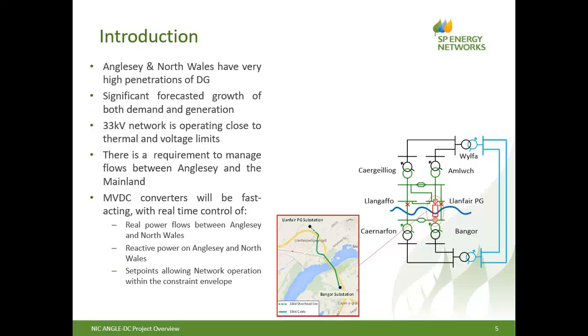We've got the added complication that when Wylfa, the new Horizon nuclear station, comes on stream, the output of that being about 2.8 gigawatts will actually cause about 50% of the circuit capacity on the 33 kV to be used up just on the kind of leakage parallel path of the power transmission from Wylfa across into mainland Wales and England. So one of our solutions to deal with this is to look at how we manage those power flows, and the MVDC route has been one that we've been keen to explore and obviously turn into a trial project.